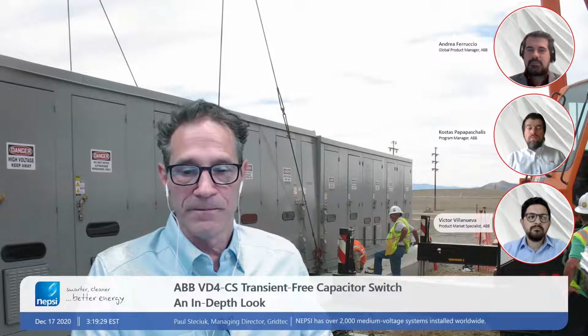And a lot of times that's to prevent resonance. Remember, filters are installed for 3 reasons. One is for power factor correction. Two is to prevent resonance, and the third is actually to reduce voltage distortion. But the second one, prevent resonance, is to prevent amplification of the harmonic current. So that's the iron core reactor that does that. That is an independent issue to switching transients, and that's really what I'm trying to get to here. Harmonic voltage distortion, harmonic filtering, and harmonic current amplification is an issue related to harmonics and the capacitor reactance and the capacitor bank resonating with the source impedance. It is not related to switching transients, which is what this switching device is doing. We oftentimes would see this VD4-CS applied with a harmonic filter, which would contain that tuning reactor. So good question.